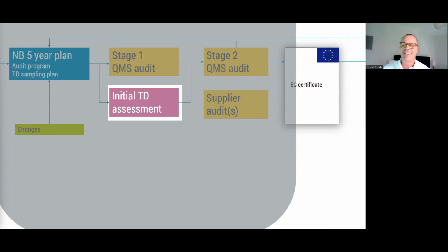And as you might now understand, this timing here can sometimes be a bit tricky for the notified body, and potentially, of course, leads to delay. This, since the output of the technical documentation assessment is depending very much on the quality of the technical documentation sent in by the manufacturer, you. So my best tip to all of you is to send in only complete and well-structured technical documentation, which I will come back to soon.